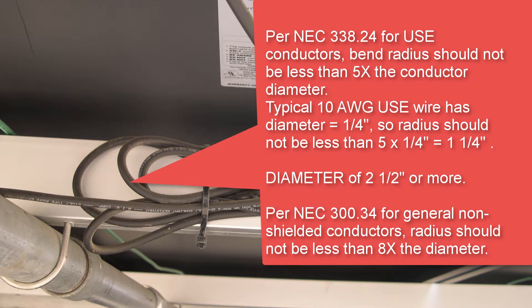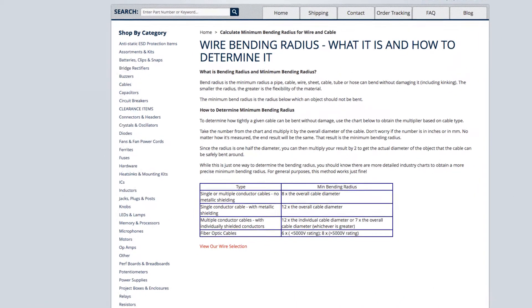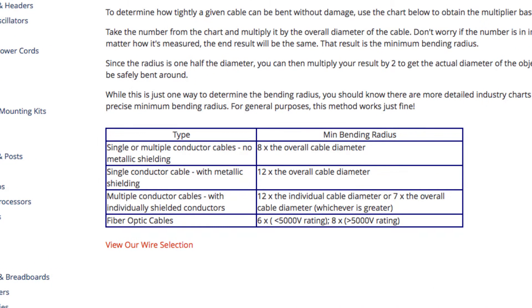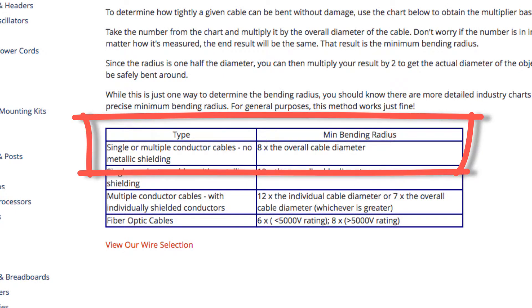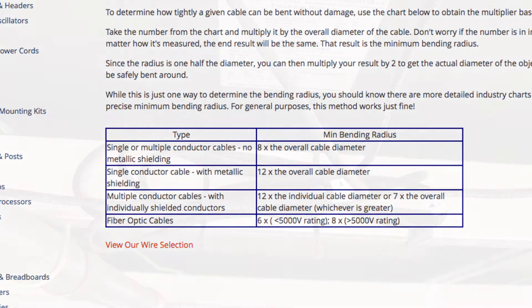That means the diameter of any bend should be at least two and a half inches or more. The code in a different section goes on to say that for general non-shielded conductors, the radius should be not less than eight times the diameter. Different manufacturers might have different specifications. For single or multiple conductor cables with no metallic shielding, the minimum bending radius they recommend is eight times the overall cable diameter.